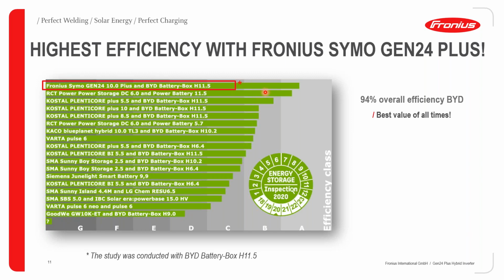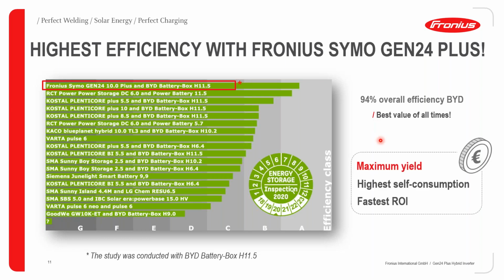So out of all the manufacturers that were tested for hybrid inverters, the Fronius Gen24 Plus with BYD battery box HV 11.5 kilowatt emerged first position with a rating of A as efficiency class. And this means that the considered energy overall efficiency was about 94%, and therefore this gave the best value of all times. So all the inverters tested before that had not achieved this kind of figure, but the Gen24 Plus inverter was able to surpass any figures that had been tested before that.